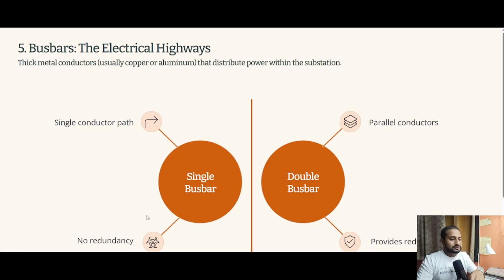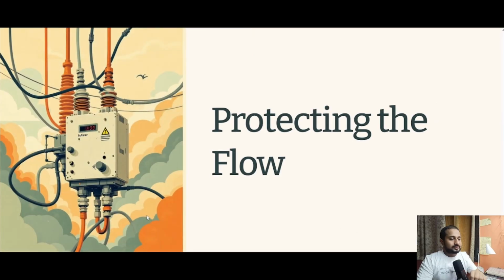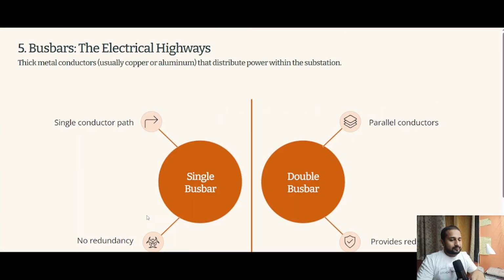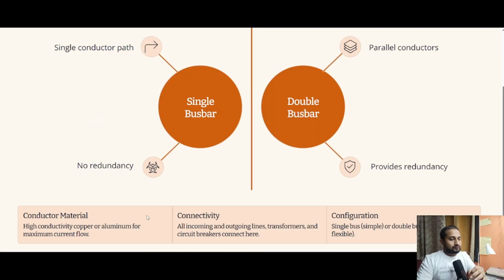In a single bus bar system, there is a single conductor path and they have no redundancy. In a double bus bar system, there are parallel conductors which provide redundancy. Means if we have to shut down one bus bar system for maintenance purpose, then the second bus bar system can operate in parallel. Then what are the materials used? High conductivity copper or aluminum for maximum current flow, connectivity for all incoming and outgoing lines, transformers, and circuit breakers. Then configuration can be, as we have discussed, single bus bar system or double bus bar system.